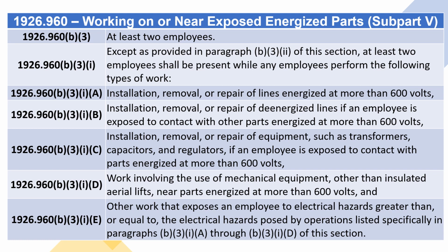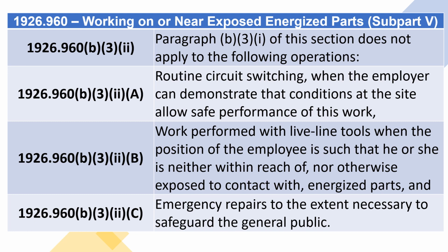Work involving the use of mechanical equipment other than insulated aerial lifts near parts energized at more than 600 volts, and other work that exposes an employee to electrical hazards greater than or equal to the electrical hazards posed by operations listed specifically in paragraphs (b)(3)(i)(A) through (D) of this section. 1926.960(b)(3)(ii). Paragraph (b)(3)(i) of this section does not apply to the following operations. 1926.960(b)(3)(ii)(A) through (C). Routine circuit switching, when the employer can demonstrate that conditions at the site allow safe performance of this work. Work performed with live-line tools when the position of the employee is such that he or she is neither within reach of, nor otherwise exposed to contact with, energized parts, and emergency repairs to the extent necessary to safeguard the general public.